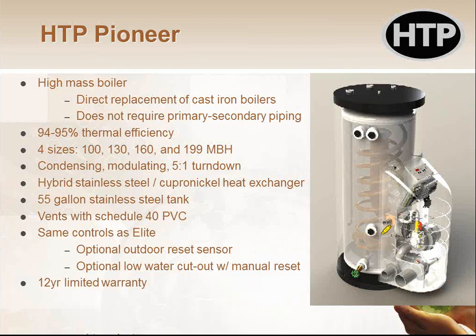Right, so in this case, instead of having the water in the tube and the flame around it, we have the flame in the tube and water surrounding it. So this is basically a condensing boiler right here, bolted to the side of a 55-gallon drum. That's probably the best way that I can describe it, although I'm sure the manufacturer has a sexier way, right?